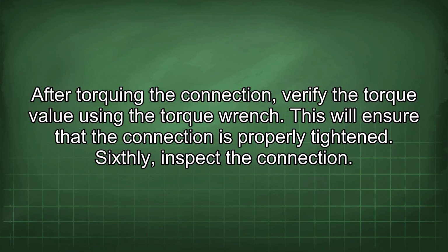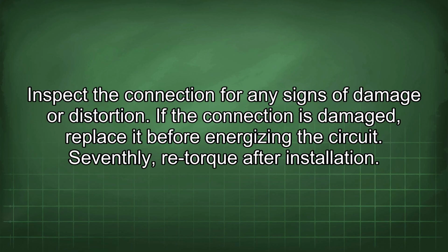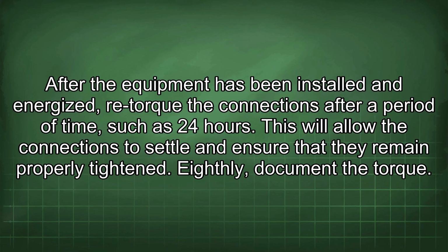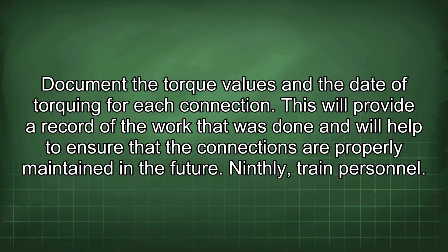Sixthly, inspect the connection. Inspect the connection for any signs of damage or distortion. If the connection is damaged, replace it before energizing the circuit. Seventhly, re-torque after installation. After the equipment has been installed and energized, re-torque the connections after a period of time, such as 24 hours. This will allow the connections to settle and ensure that they remain properly tightened. Eighthly, document the torque. Document the torque values and the date of torquing for each connection. This will provide a record of the work that was done and will help to ensure that the connections are properly maintained in the future.